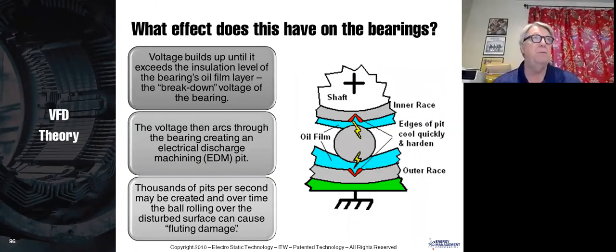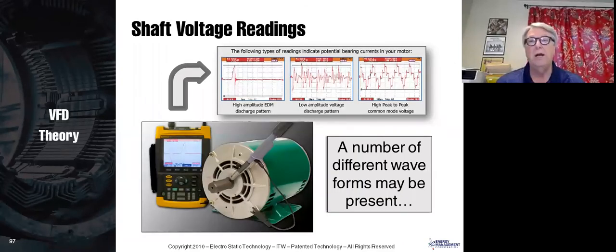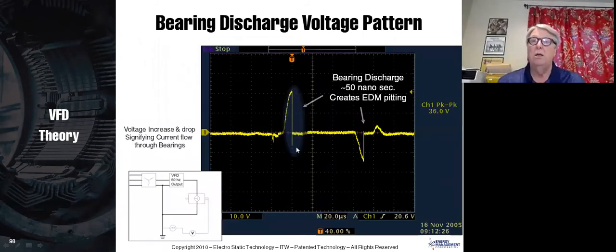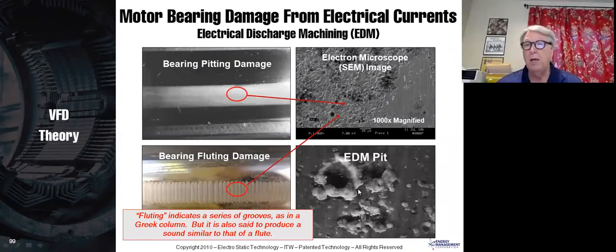What is between the frame and the shaft of the motor? The bearing. So if those voltages get too high, they can arc through the bearing, and they begin to pit the bearing and pit the bearing race. You can actually measure these voltages with a device like this that has a brush that you can touch to the frame, and you need to have at least a 200 megahertz scope, and you can see those voltages. Now, here's a voltage that's going up, and then boom, it drops suddenly. What causes it to drop suddenly? It just discharged through your bearing. It just welded a little hole in your bearing, and it looks like this.